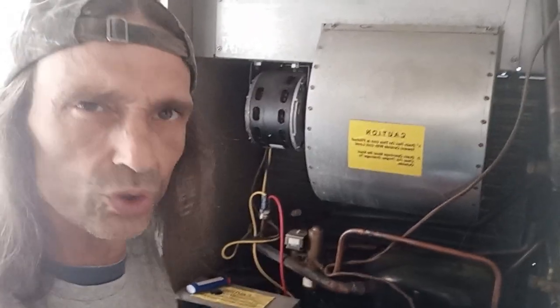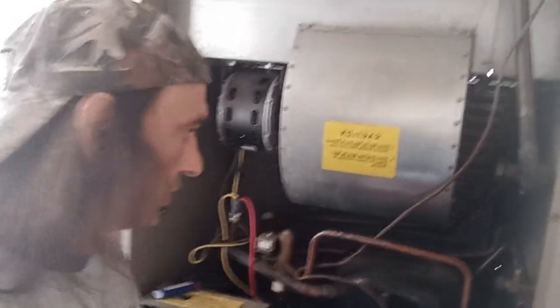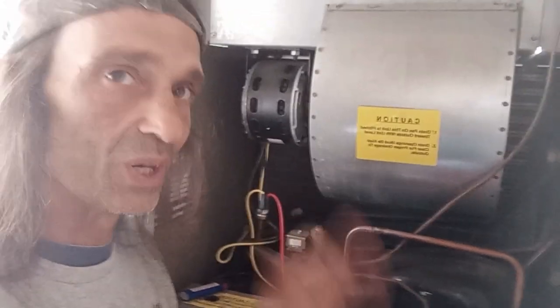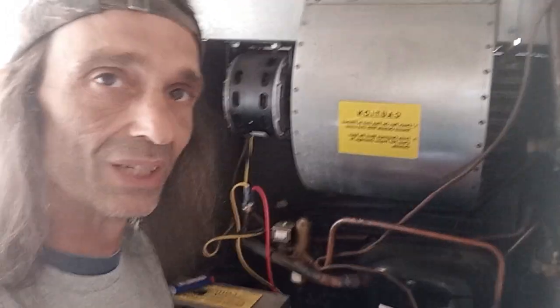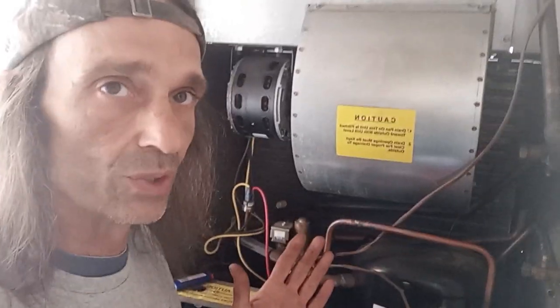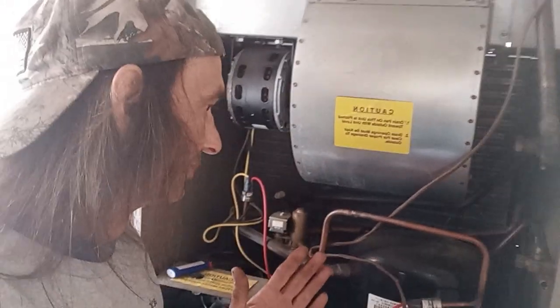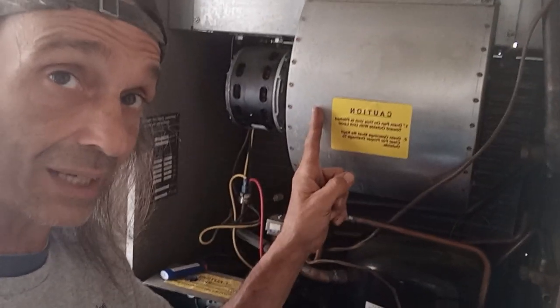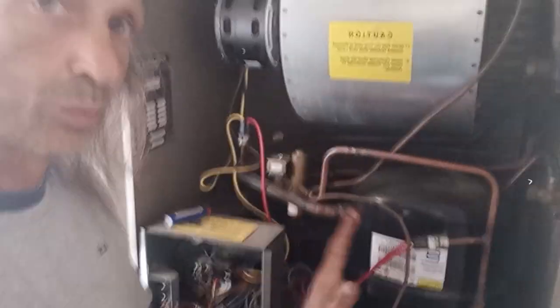Here's what we're going to do with this coil. Changing an evaporator coil is about $3,000 — we're done, though you might wait a week to get it. If it's still good two years later, you didn't make a bad decision. This condenser coil is made to come in from this way: the fans have to come out, the fan housing comes out, the compressor comes out, the control box comes out, the reversing valve and all associated piping and accumulator have to come out.